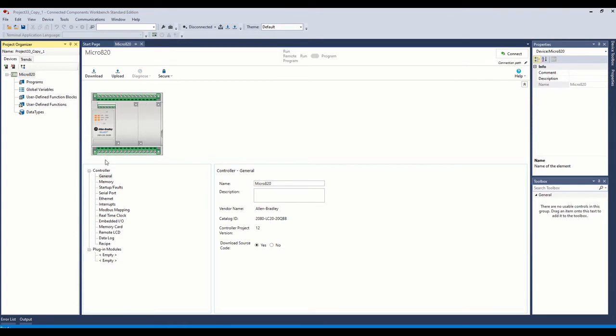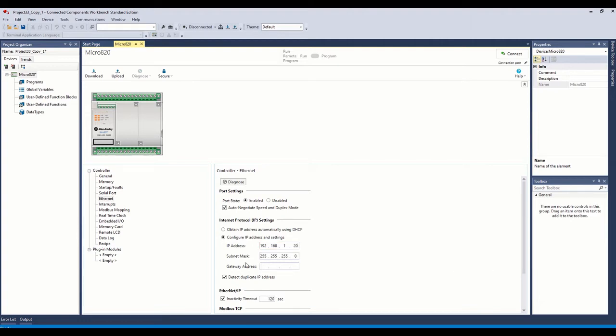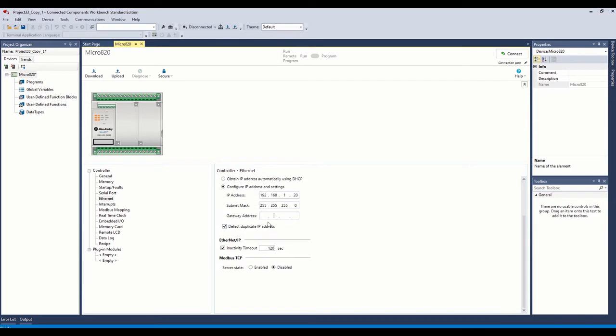In order to do this, the first thing we need to do to set up our Modbus over TCP is we need to come to the Ethernet port setup. We're going to go ahead and put our static IP address of the controller I have here. I'm going to leave the gateway blank. You can put one in here if you're using a gateway. I'm going to turn this duplicate IP off. And then down here under the Modbus TCP server, the server state, we want to just click Enabled on that.